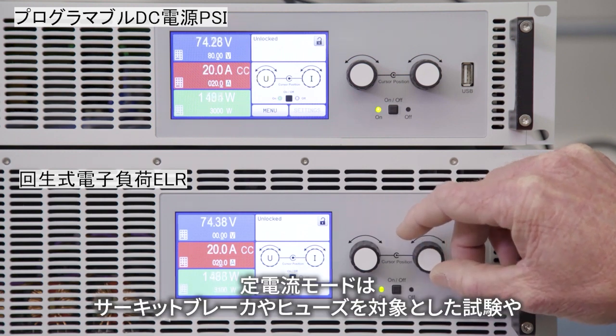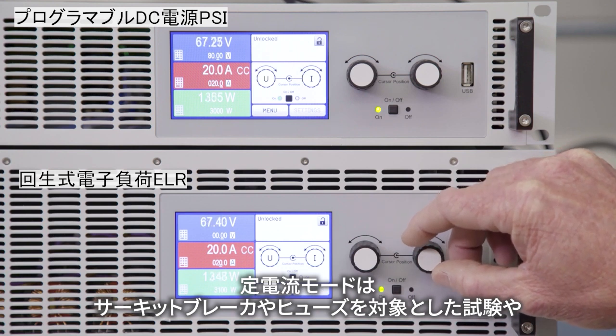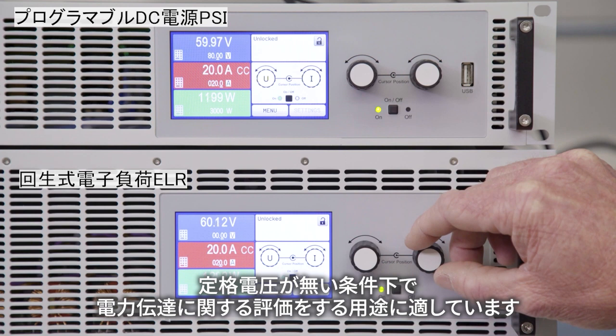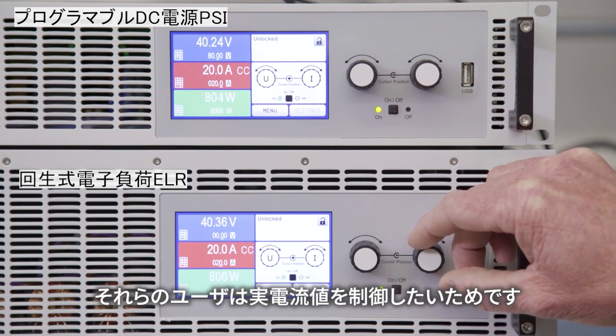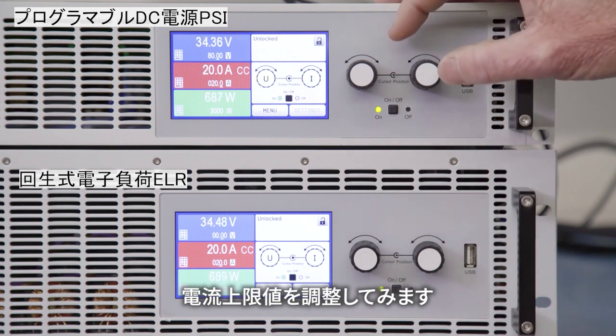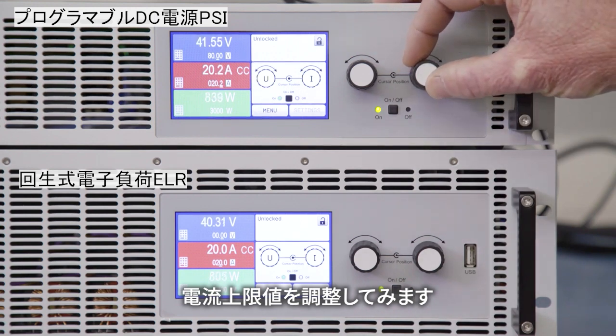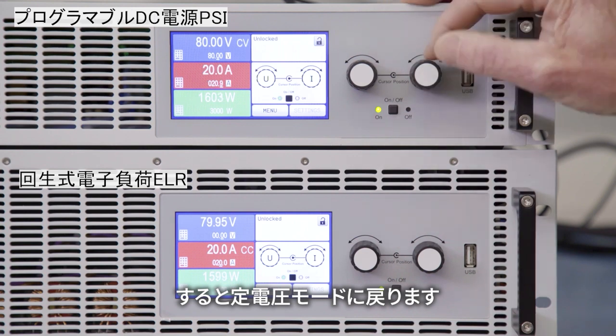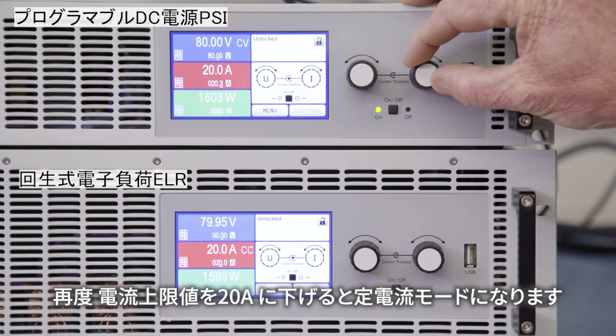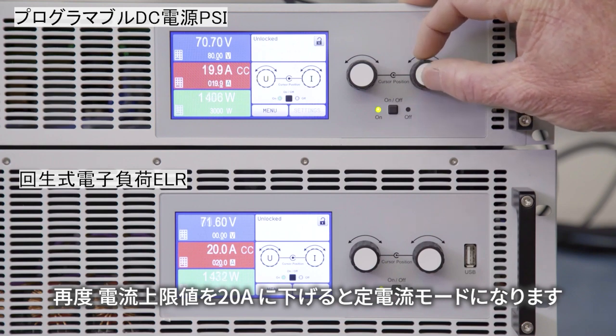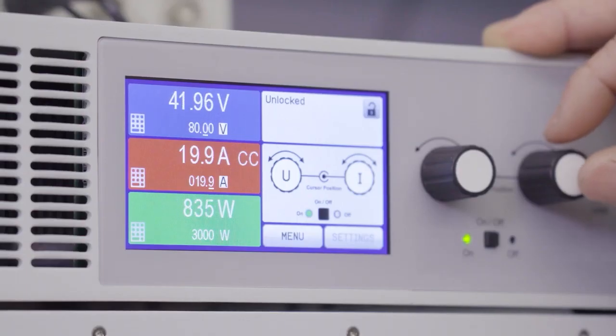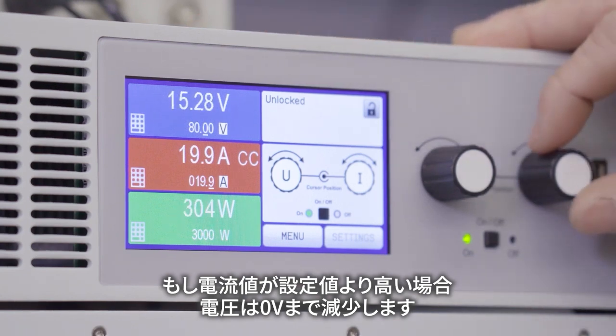Constant current mode can be useful in applications such as circuit breaker testing and fuse testing, where the reference voltage is not necessarily the most important portion of the power being delivered, and users are more interested in controlling the actual current levels. That current can of course be adjusted. You can program the current limit. If you want to go back into constant voltage mode, simply increase the current limit, and you can also take the current back down to force the power supply back into constant current mode. As you see, the voltage will ramp down, all the way to 0 volts, if you program higher currents.